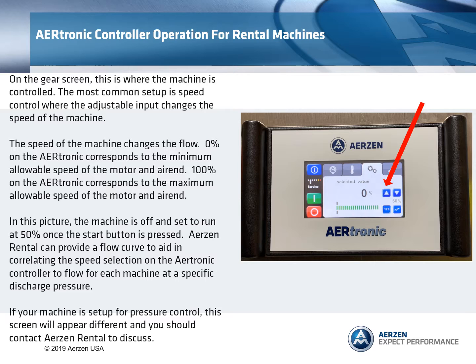0% on the AERtronic corresponds to the minimum allowable speed of the motor and air end. 100% on the AERtronic corresponds to the maximum allowable speed of the motor and air end. In this picture the machine is off and set to run at 50% once the start button is pressed. Aerzen Rental can provide a flow curve to aid in correlating the speed selection on the AERtronic controller to flow for each machine at a specific discharge pressure.